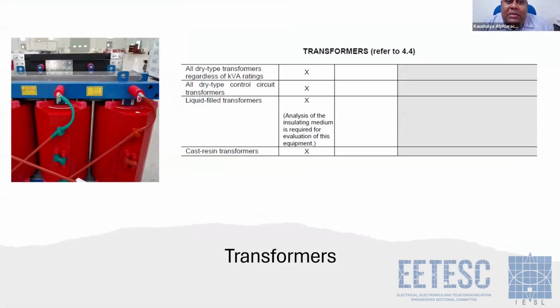All dry type transformers, regardless of kVA rating, isolation transformers, auto transformers and all dry type control circuit transformers: replace. Liquid filled transformers, they said replace, but that depends on the damage that happened. So you have to do a pre-test and see whether your transformer is in a condition to rehabilitate or recondition or not.